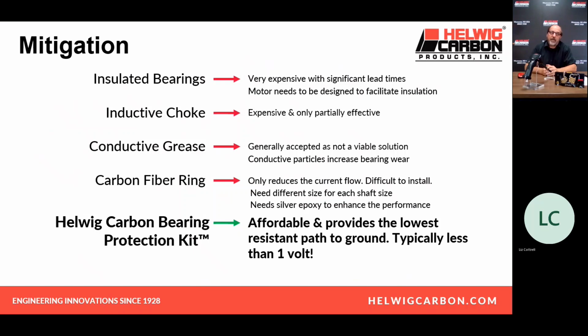Now, we've determined that you have a problem. Your motor is driven from a pulse width modulated source, a variable frequency drive. We see that it's damaging your bearings. We talked about some of the cause and effect of that: burnt grease, fluted raceways, things of this nature. And there are a bunch of different mitigation solutions out there. Let's talk about just a few of them.